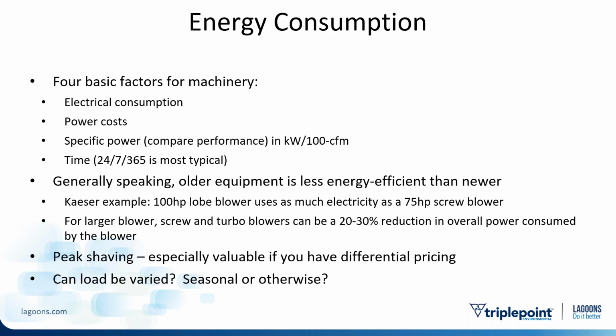It's important to know that generally, older equipment is less energy efficient than newer equipment. Our friends at Kaeser have a great example—they have a presentation on the internet you can download to learn more about their equipment and its energy efficiency. They show a 100 horsepower lobe blower using as much electricity as a 75 horsepower screw blower, and for larger blowers, screws and turbos, you can see a 20 to 30% reduction in overall power consumed.